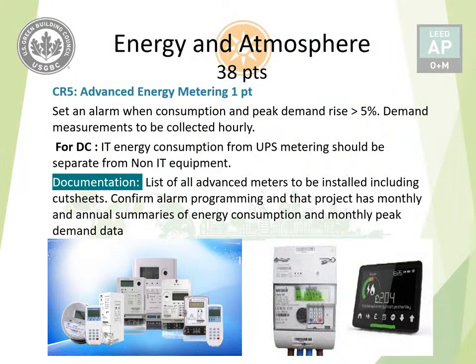Similarly for energy, IT energy consumption from UPS metering should be separate from non-IT equipment. For documentation: a list of all advanced meters installed on site and how they will be programmed - you can submit data sheets and alarm programming details, such as when the alarm will sound at more than 5%, or maybe tweaked to 4%. The project should have monthly and annual summaries for energy consumption and monthly peak demand data.